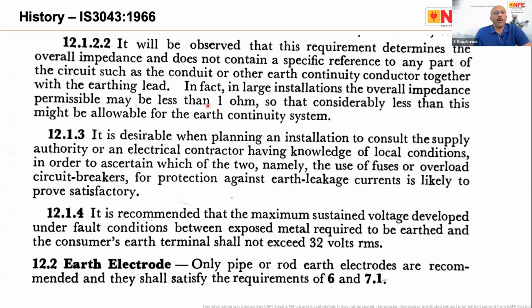I don't know on what background these are written. 1 ohm, the earth continuity resistance. So even today, the 2018 version of IS 3043 contains similar wording on earth continuity: the maximum continuity resistance of the earth fault return path shall be less than 1 ohm. So all these are still there.